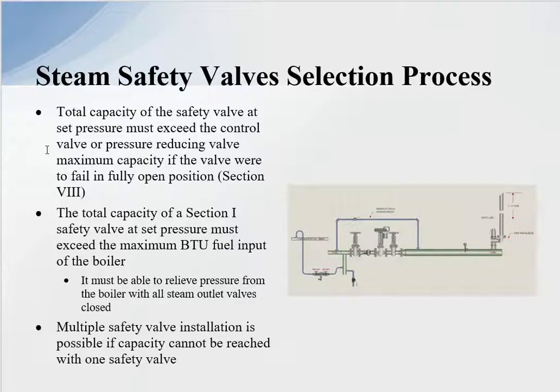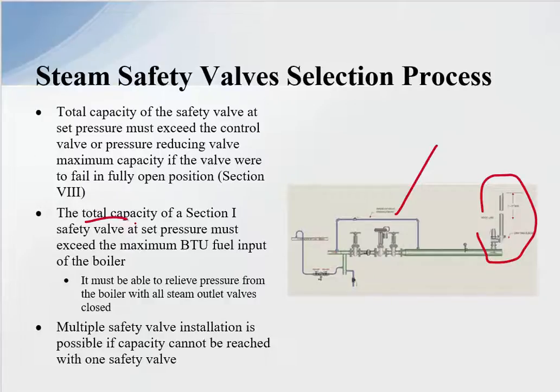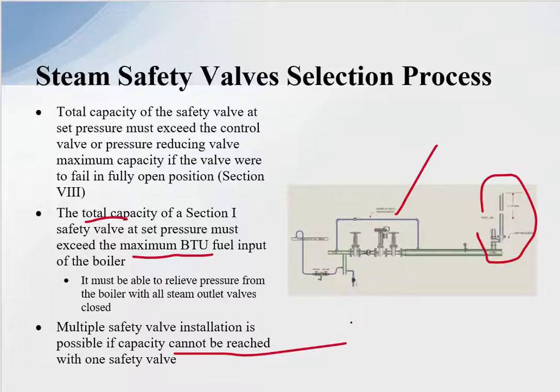The total capacity of the safety valve at set pressure must exceed the maximum capacity of the control valve or pressure reducing valve if it were to fail in the fully open position. So if that valve fails fully open, the safety valve must be able to discharge the total capacity. For boilers, that means the safety valve must relieve the maximum steam output corresponding to the maximum BTU fuel input for that boiler, depending on fuel type. Multiple safety valve installation is possible if the required capacity cannot be met with one valve — it is common to find two or three safety valves on boilers.